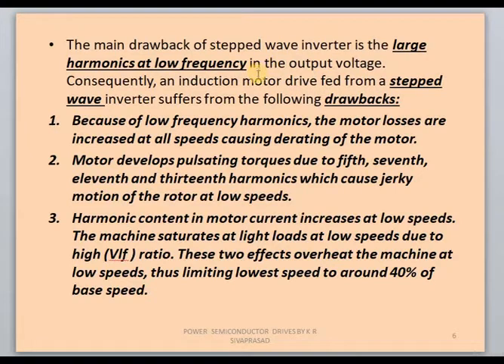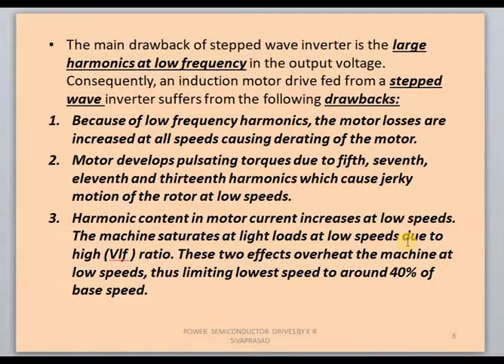These are the drawbacks of the stepped wave inverter. The major drawback is it produces harmonics at low frequency. Due to these harmonics it produces more losses in the machine and the de-rating of the machine increases, reducing efficiency. It also produces a pulsating torque at low frequency, creating jerky motion at low speed operations. There is a possibility of overheating at low speeds. Therefore speed control is limited to about 40% of base speed using this method.